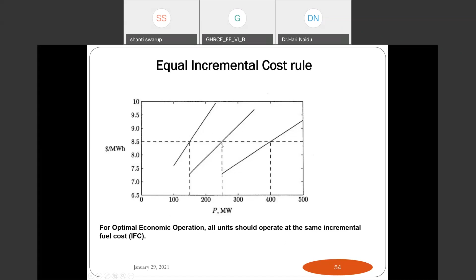This is the power generation, for this incremental fuel cost curve, which should intersect all at the same point. For optimal economic operation, all units should operate with the same incremental fuel cost curve. Unit 1 has 8.5, Unit 2 has 8.5, Unit 3 has 8.5. If all of them have the same incremental fuel cost curve, then optimal economic operation has been reached.